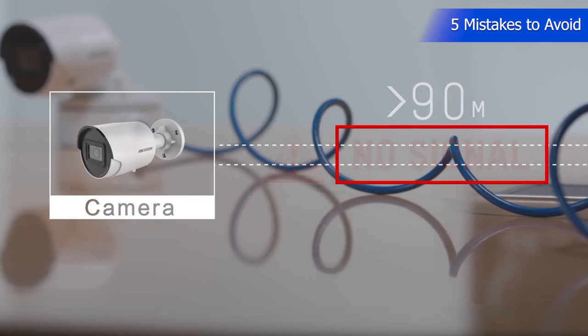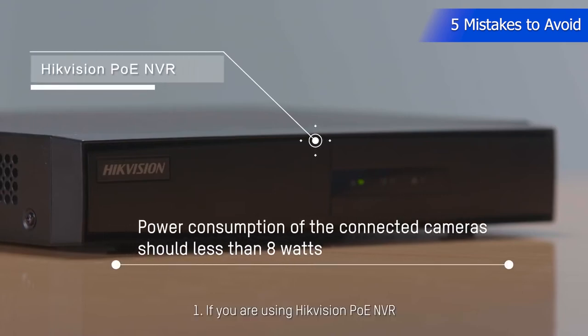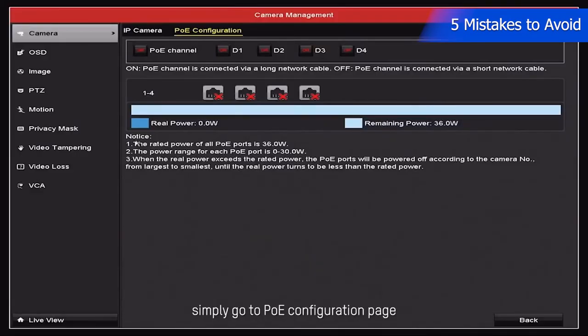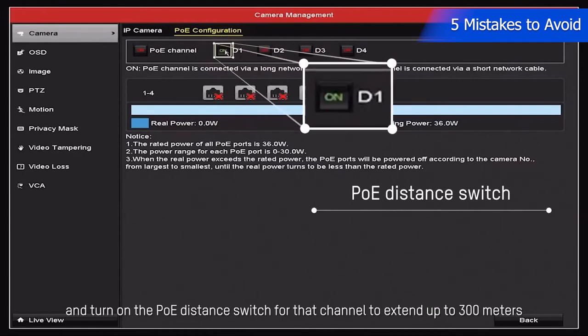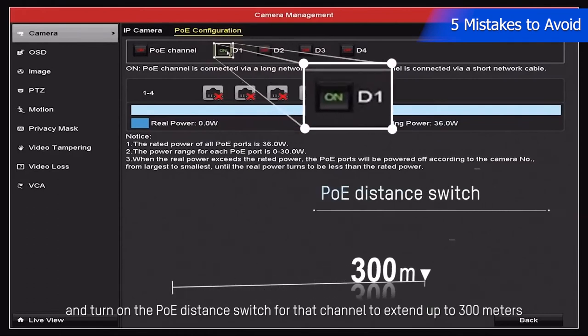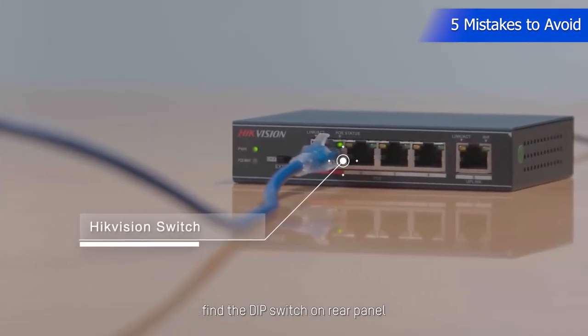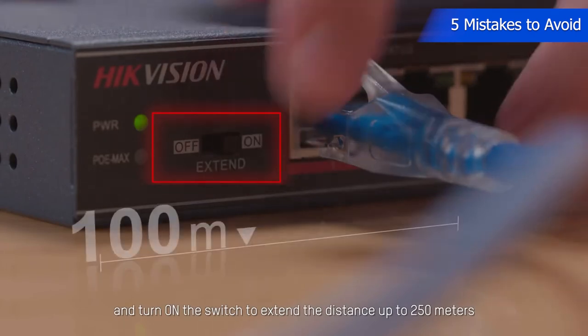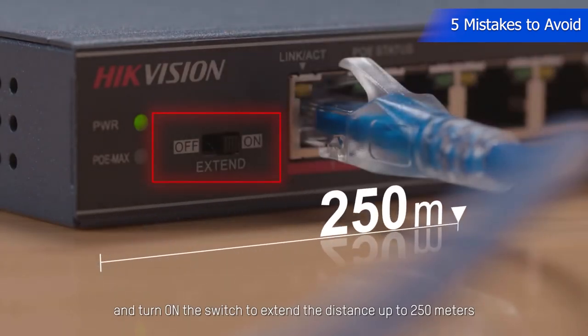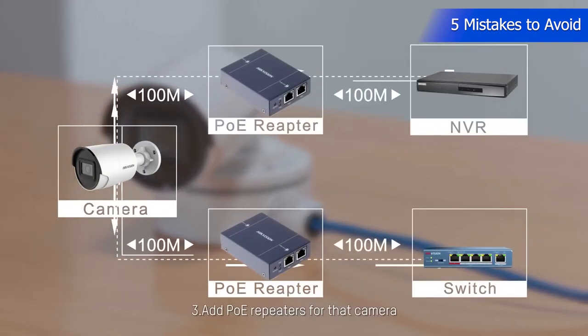If you need wires connecting the camera to support longer distances, try these options. If you are using Hikvision PoE NVR, simply go to the PoE Configuration page and turn on the PoE Distance switch for that channel to extend up to 300 meters. If you are using Hikvision switches, find the DIP switch on the rear panel and turn on the switch to extend the distance up to 250 meters. You can also add PoE repeaters for that camera.